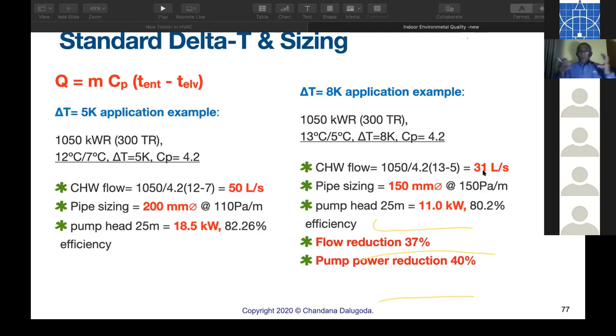So you can have smaller piping, smaller pumps, because pipe sizing is 150 instead of 200. Pump head 25 meter, now your pump selection is 11 kilowatts instead of 18.5. That is also 80% efficiency. See, flow reduction is 37% and pump power reduction 40%. So we need high delta T, but ASHRAE also gives their limitations.